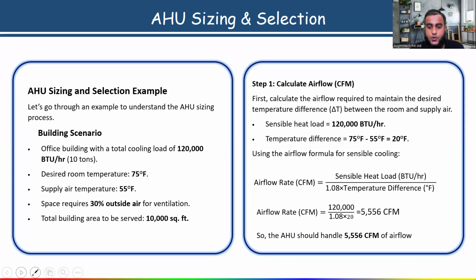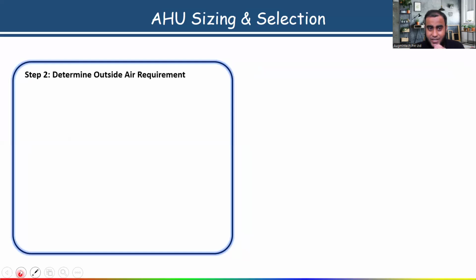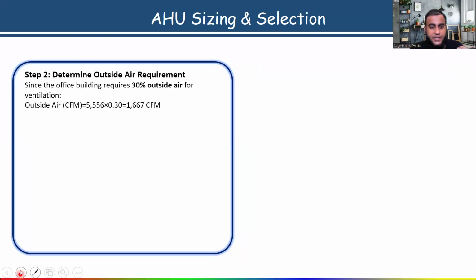Next, the AHU which you are selecting should handle 5,556 CFM of airflow. Now the next detail which we have to submit to the manufacturer is that we need to determine the outside air requirement. Here we are assuming 30% for an office building, but the exact calculation I have shown you. So 30% of that total, we have got 1,667.